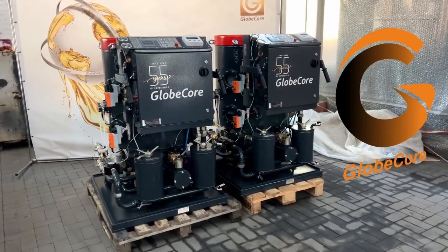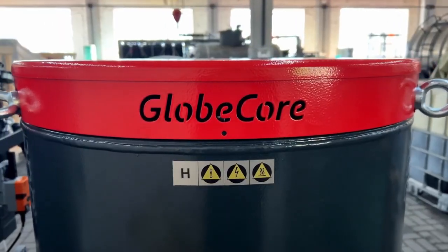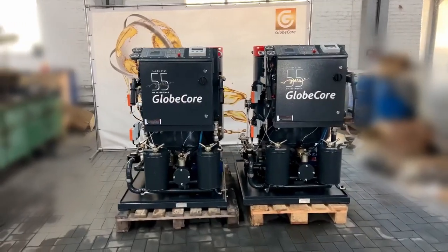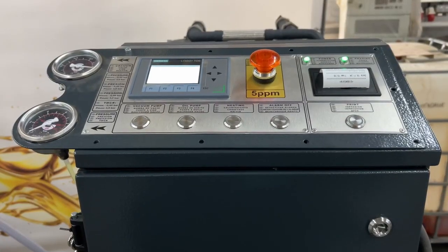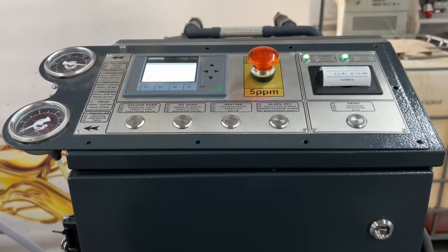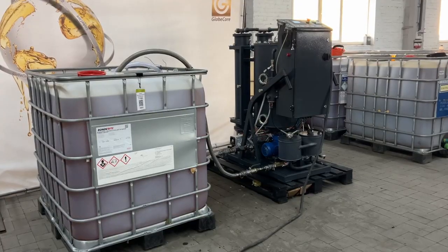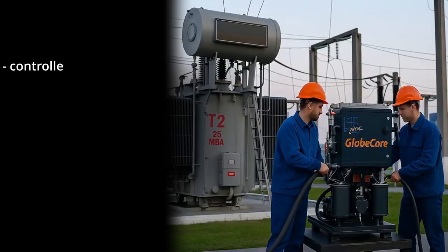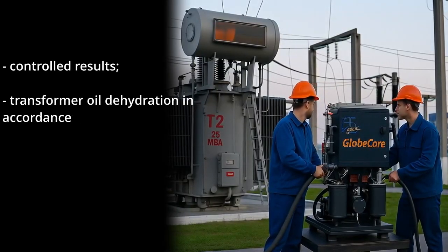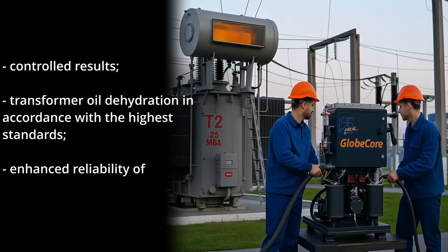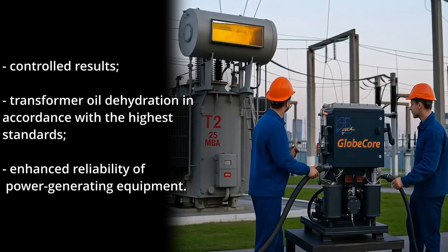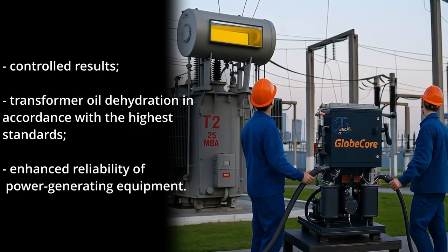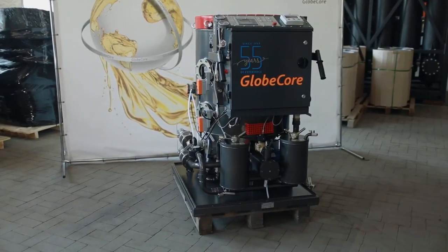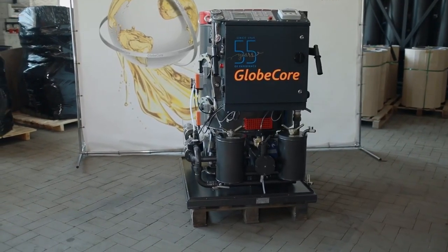This is essential for the service companies and manufacturers that must prove the quality of their services by the appropriate documents. Owing to the GlobeCore CMM machines operating in 5 ppm and 5 ppm plus modes, you achieve the following: controlled results, transformer oil dehydration in accordance with the highest standards, enhanced reliability of power-generating equipment.